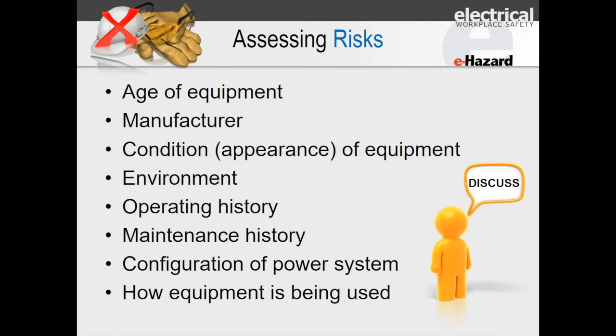The operating history and the maintenance history are very, very important. In fact, for the maintenance history, if you look at Annex B in CSA Z462, it gives you some good guidance, and certainly the guideline CSA Z463 in Canada, which is the maintenance guideline, or NFPA 70B in the US. The configuration of the power system: have you got a tie breaker that's closed? How's the equipment being used?